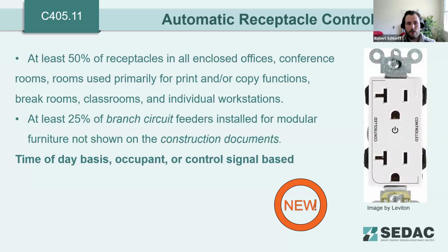on the construction documents. Just to cover automatic receptacles, these are receptacles that are set up and controlled so that if someone forgets to turn something off, the receptacle itself will turn off whatever device is plugged into it. Some items that might be good for these are cup warmers, office space heaters, small fans, other small appliances, potentially other electronic devices if it's not going to interrupt any processes by being turned off. But essentially, these automatic receptacles are going to turn off the things that occupants typically forget to turn off.